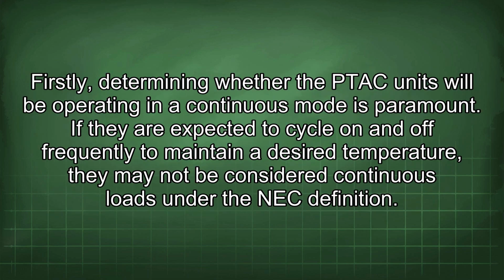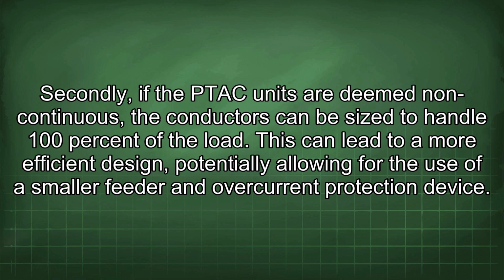Firstly, determining whether the PTAC units will be operating in a continuous mode is paramount. If they are expected to cycle on and off frequently to maintain a desired temperature, they may not be considered continuous loads under the NEC definition. Secondly, if the PTAC units are deemed non-continuous, the conductors can be sized to handle 100% of the load. This can lead to a more efficient design, potentially allowing for the use of a smaller feeder and overcurrent protection device.